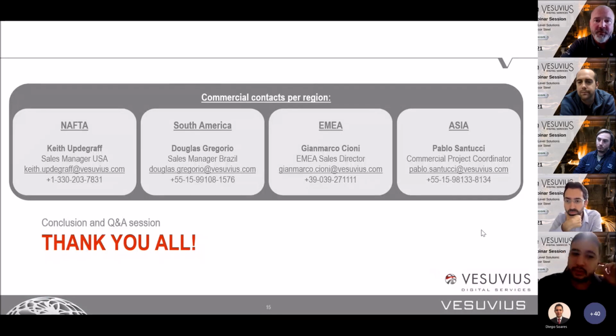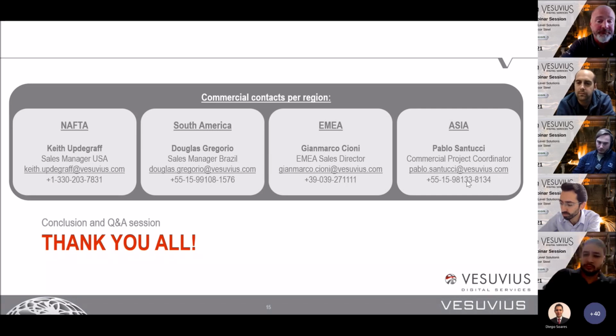One important thing about installation is that we usually don't have to interrupt manufacturing. Usually on a down day we can do the measuring, then do the background work on the algorithm and the formula that needs to be put in place. Same with level 2 - we were actually able to do that offline, testing it before we even implemented it. So it's relatively easy to install with the right support.